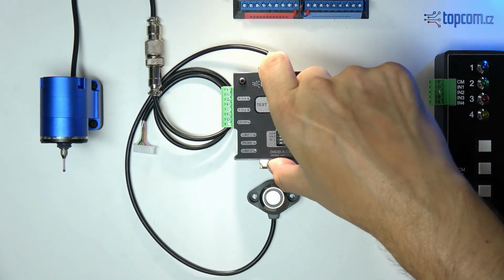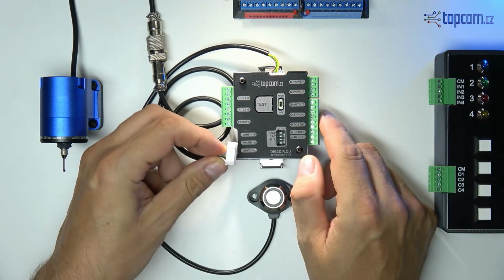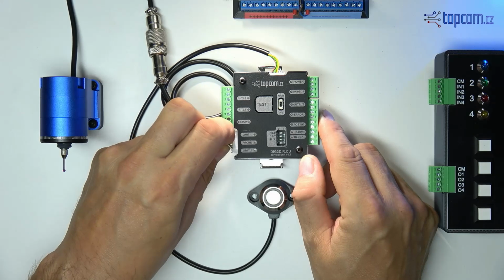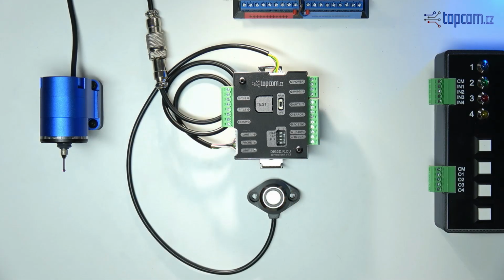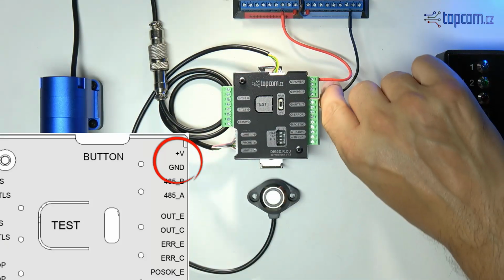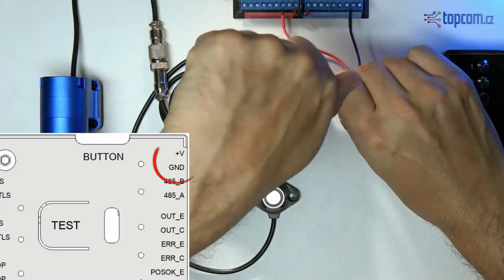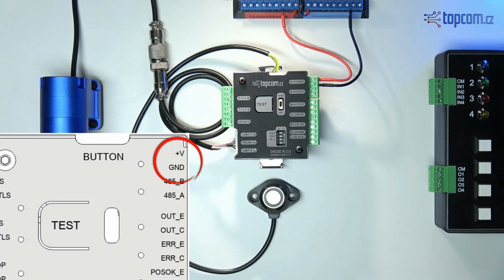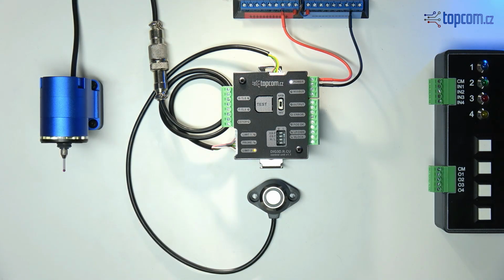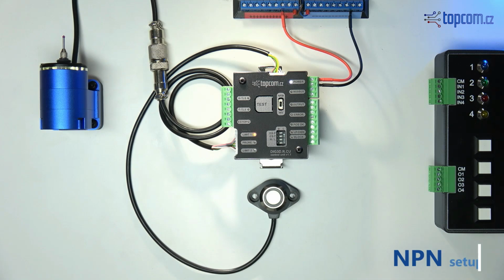First, we'll connect the manual button and the rotary probe body using their dedicated connectors. Next, we connect the control unit to a DC power supply. The voltage should be between 12 and 24 volts. When the power is turned on, the rotary probe automatically returns to its home position.